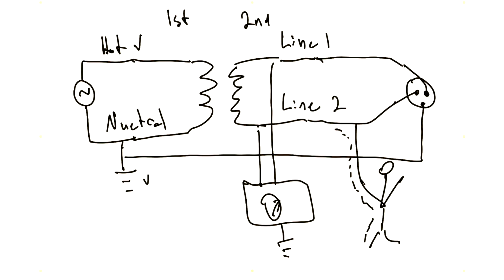Okay, so the line isolation monitor works a little differently than maybe what you're thinking, but it is basically measuring what is the potential for leakage current to occur. How much leakage current would happen had this been in a more traditional style circuit? So just because you touch line 2 doesn't mean there's leakage current going through you right now. However, there's going to be a tremendous potential for leakage current to go through you. So the line isolation monitor is going to alarm in this circumstance, but you will not be shocked.